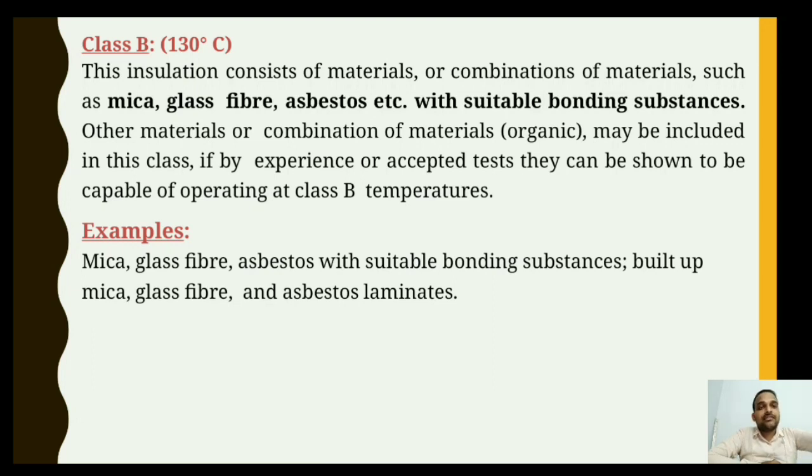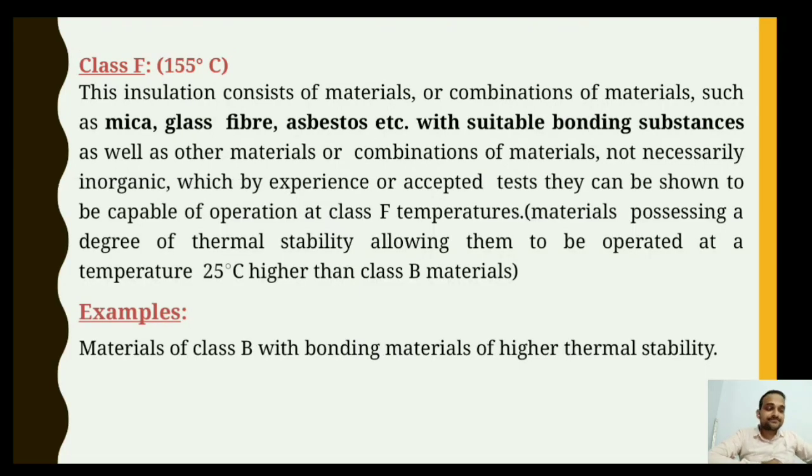Okay, now moving forward again, the class F. The fifth one is class F, and the temperature range is up to 155 degrees Celsius. In this class, the organic and inorganic substances get bonded with each other. In the previous class we have seen that the organic compound is bonded with inorganic, that is, the parent is organic and the substrate, we can say, is the inorganic substance.